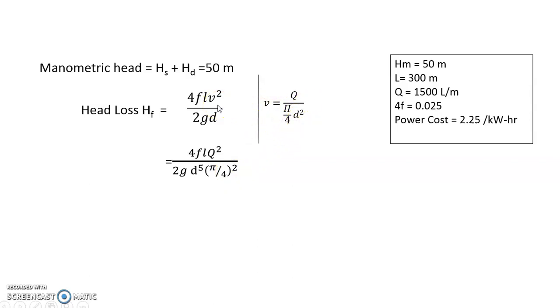Just that we have substituted Q by π/4 d² for velocity here. So for 4f being 0.025, L equals to 300 meters, and Q is 1500 liters per minute. Again convert this to meter cube per second: 1500 liters is 1.5 meter cube per minute, just converted into seconds. So hf in such a way calculated is hf equals to 38.77 meters.